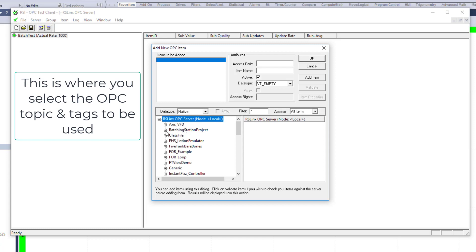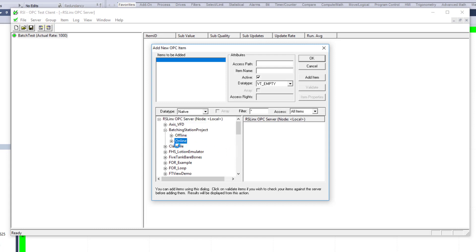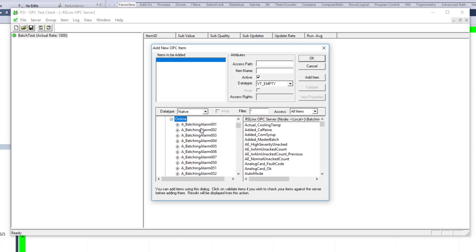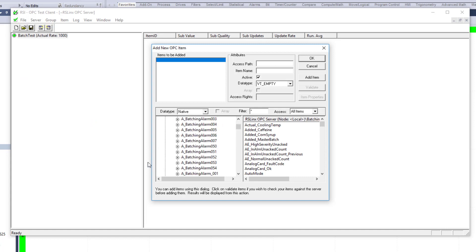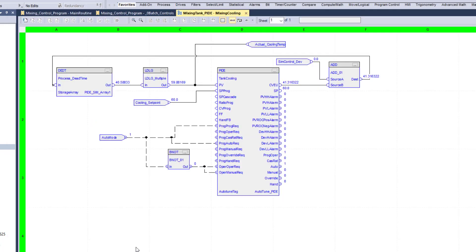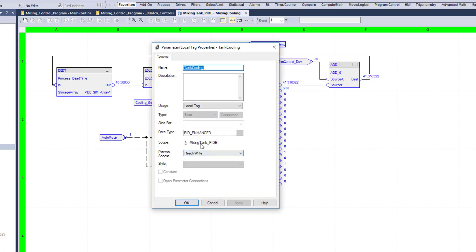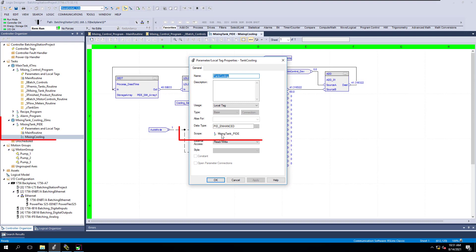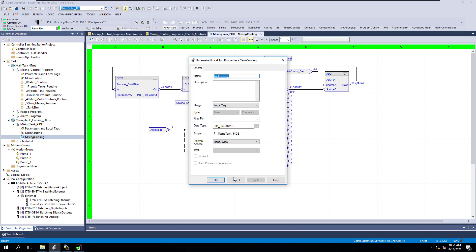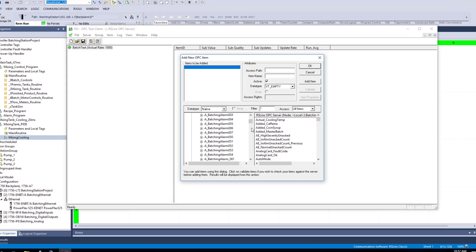Now, in this case, you get to choose from your OPC list that you currently have active. In this case, we have our batching station. So we're going to get our online tags. We can get just about anything we want, but in this case, let's come in here and get this PID information. So this is the cooling tank. Let's make sure, for one, where it is. It's inside of the mixing tank PID, that's the scope of the tag, if you would. So this scope of the tag is not at controller level, it's at program level. So let's keep that in mind.